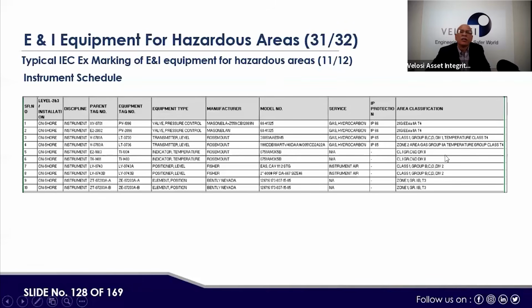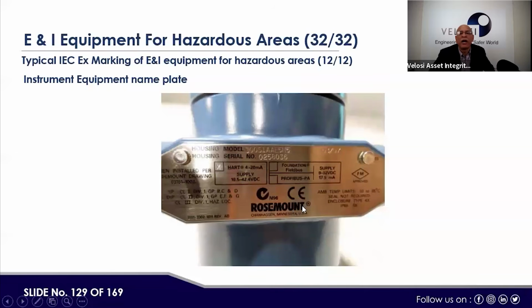And then if we have to make an equipment list for the instruments available in any area, we make the list of those equipment and instrument tag numbers as per the SAP hierarchy. Like here: installation, discipline, parent tag, equipment type, manufacturer, model, service, then IP protection and area classification. So this way we try to look at the applicable safety class of those particular explosion proof equipment. And as a data sheet also you will find the nameplate data for explosion proof, like here IEC 60079 is printed on the nameplate by the Rosemount.